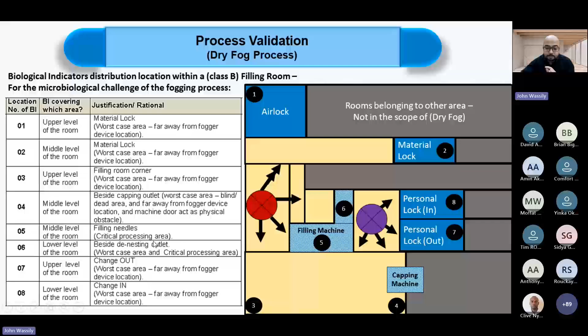So we are going to put biological indicators constituting spore-forming Geobacillus stearothermophilus microorganisms, and we will start the fogging process on them, then collect those biological indicators by the end of the program to make sure the process has been efficient in killing all the microorganisms. It's important to know that those locations have been selected based on a risk assessment, covering the worst case locations as you can see in the table beside.